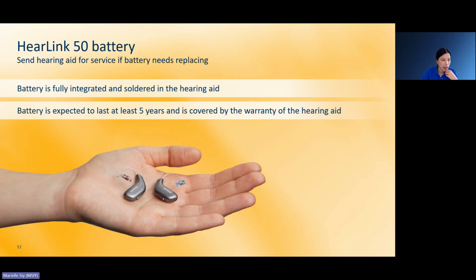This should not happen, I repeat, but if there is something wrong with the HearLink 50 or the HearLink 30 or 40, then I would recommend that before you send it for servicing, to have it checked or the battery replaced, make sure that you activate the battery protection mode in HearSuite. This protects the battery while you're transferring it.